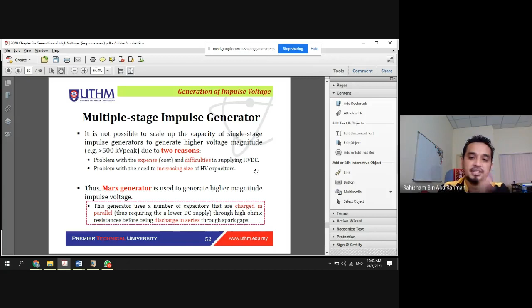What happens with the multiple impulse generator is that we charge stages 1, 2, 3, 4 and so on in parallel, meaning we don't really require a high HVDC level to charge all the circuits. We charge them in parallel and discharge them in series. That's why we only require a relatively lower HVDC, yet are able to produce a very high magnitude at the output.